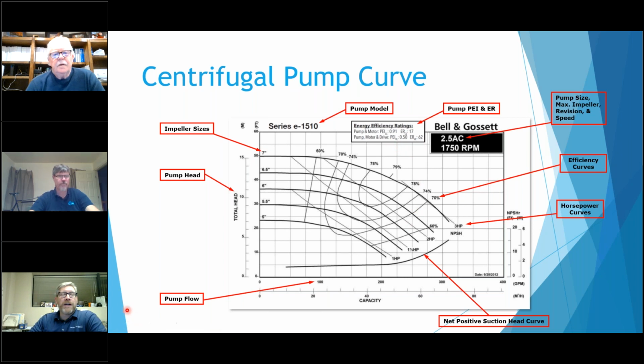The ER comes from the Hydraulic Institute, and that one's the opposite. So the higher the number, the more efficient it's going to be. I'm not sure of the whole equation, but it has to do with part loading the pump, and where it's operating, where it's expected to operate, and everything like that. So that's something new that just came out, and that affects most of the centrifugal pumps from 1510s to Series 80 inline pumps, larger base mounted double suction pumps, anything, even turbine pumps have to be rated with this as well.